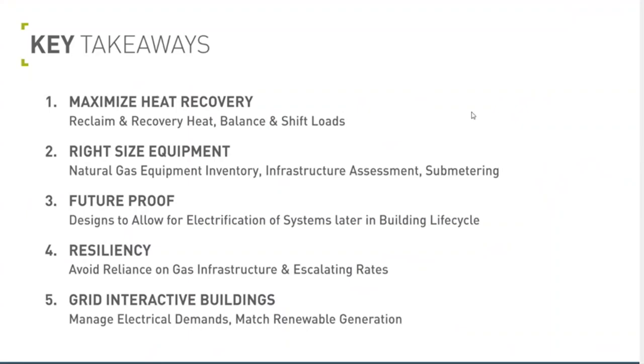Here are the key takeaways: right-size your systems. We don't want to throw in heat recovery equipment that's expensive and takes up a lot of space if you don't have the loads that make it make sense. We want those systems rightly sized to handle those loads for a cost-effective electrification solution. Understanding your loads and your annual load profiles helps you make the right decisions. Future-proof now - even if you don't have electrified systems today for your new construction project, make sure your electrical service capacity is sized correctly so you can swap out that natural gas equipment for electrified equipment later.